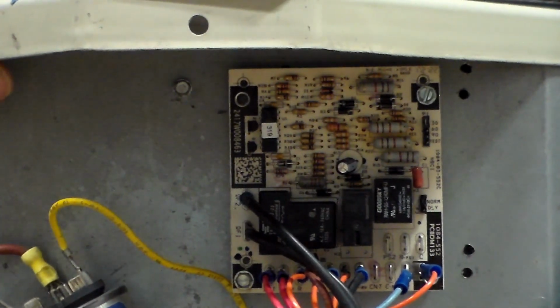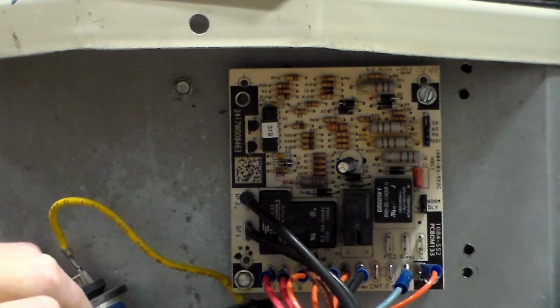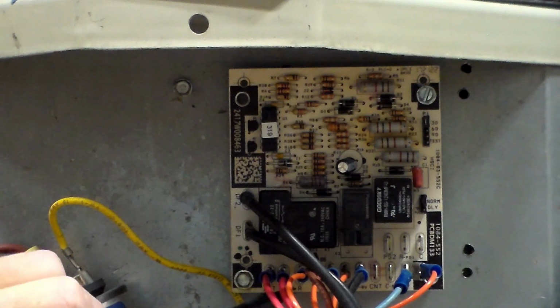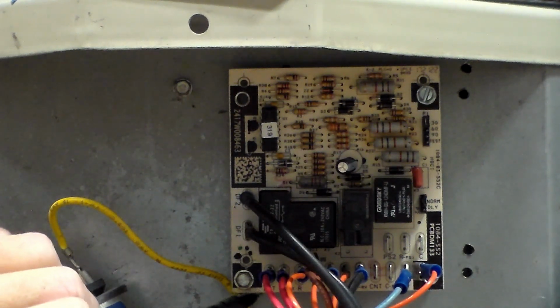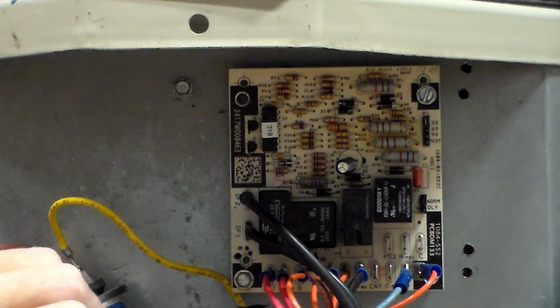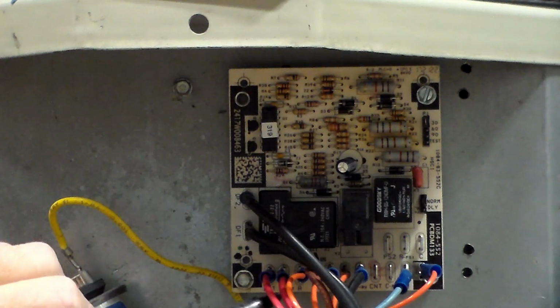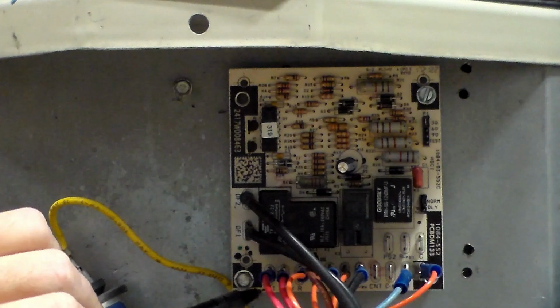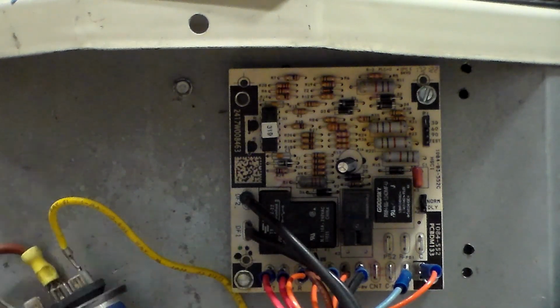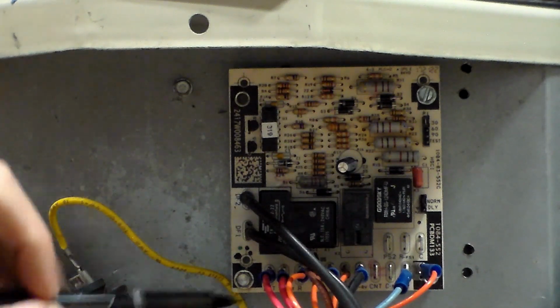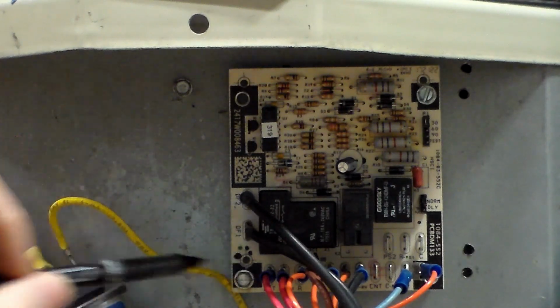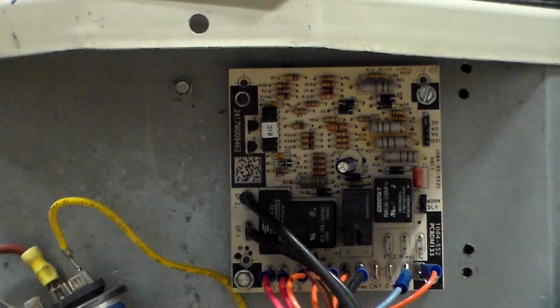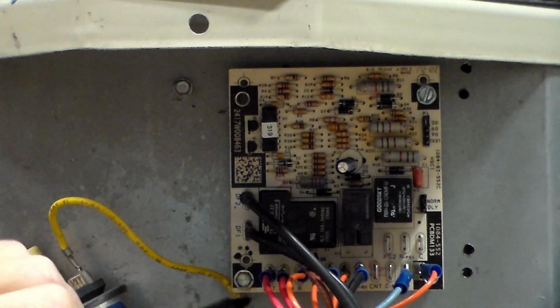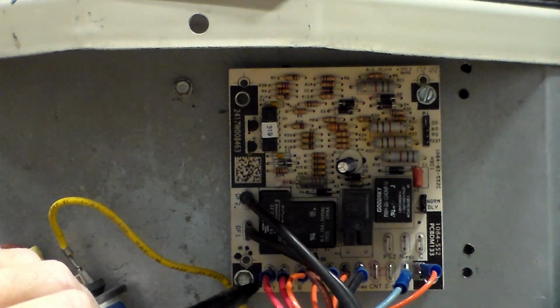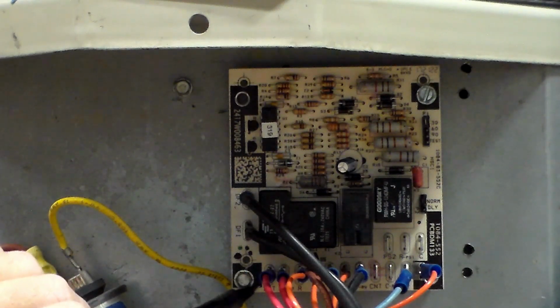The other thing that this one does a little bit different is down here, it's got DFT and R with a small DFT, right next to the R terminal. That would be your defrost sensor, your defrost termination sensor. That's what DFT stands for, defrost thermostat or defrost termination. This one is just running that R signal through the defrost termination sensor and getting it back on the DFT terminal. It could still be a thermistor or a snap disk. When it reads as open and it doesn't get that signal back here, then it knows we don't need defrost. We're warm coil. But when it does get that signal back here, then it knows it needs to go into defrost.